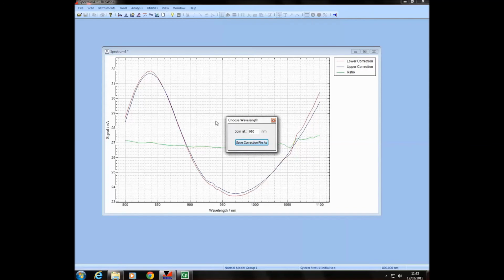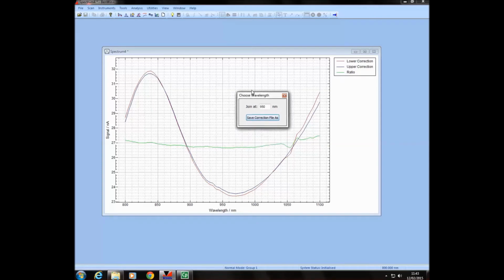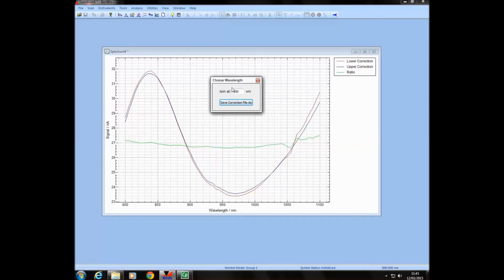And we can see here the ratio in green of the two calibration factors, the calibration factors being shown here in red and blue. We tend to automatically choose a 950 nanometer crossover wavelength. That is to say that we will take the silicon data from 300 to 950 nanometers, and thereafter we'll use the germanium data. In that manner we also avoid the band edge region of the silicon device, which has of course an inherent temperature dependence.